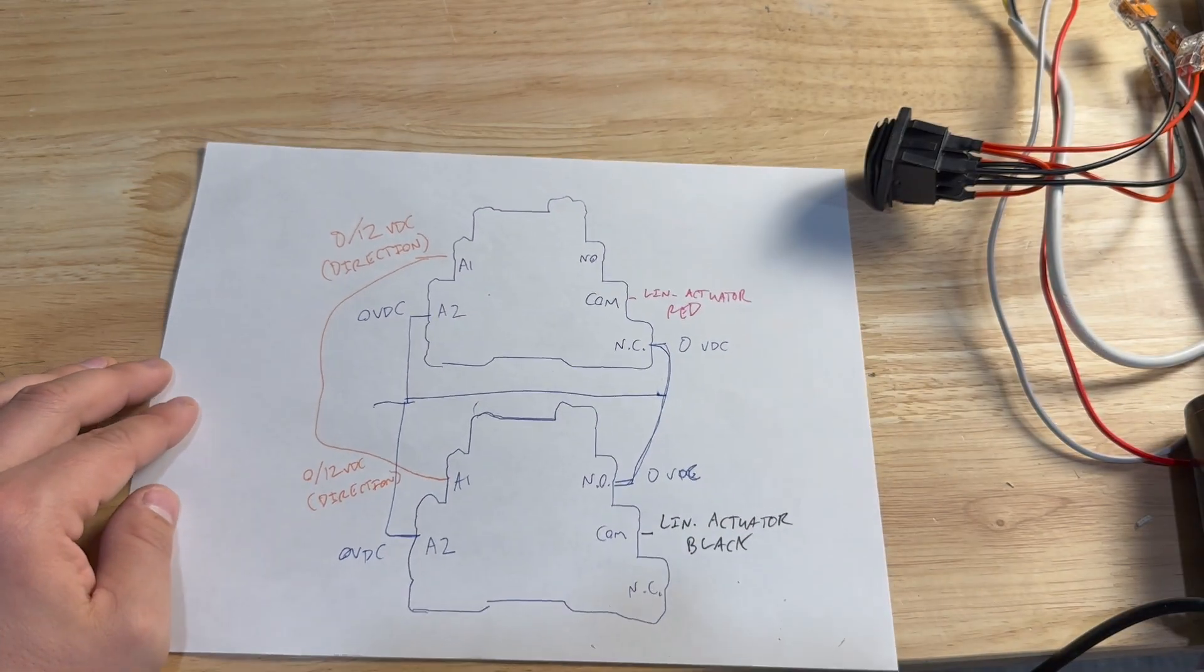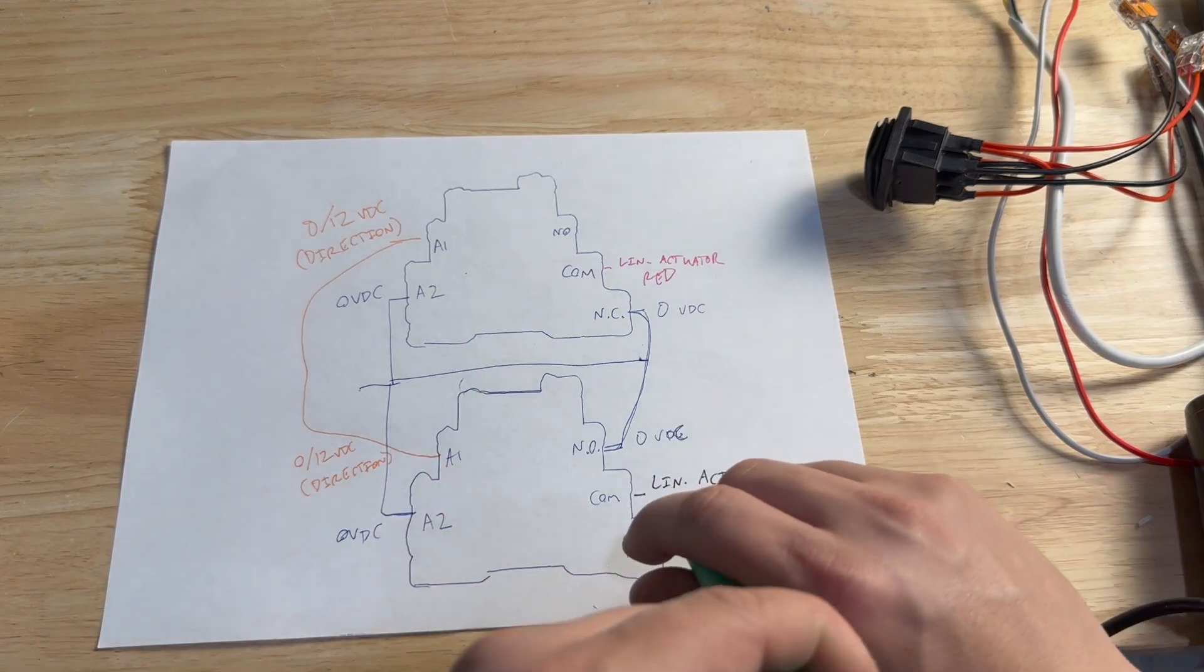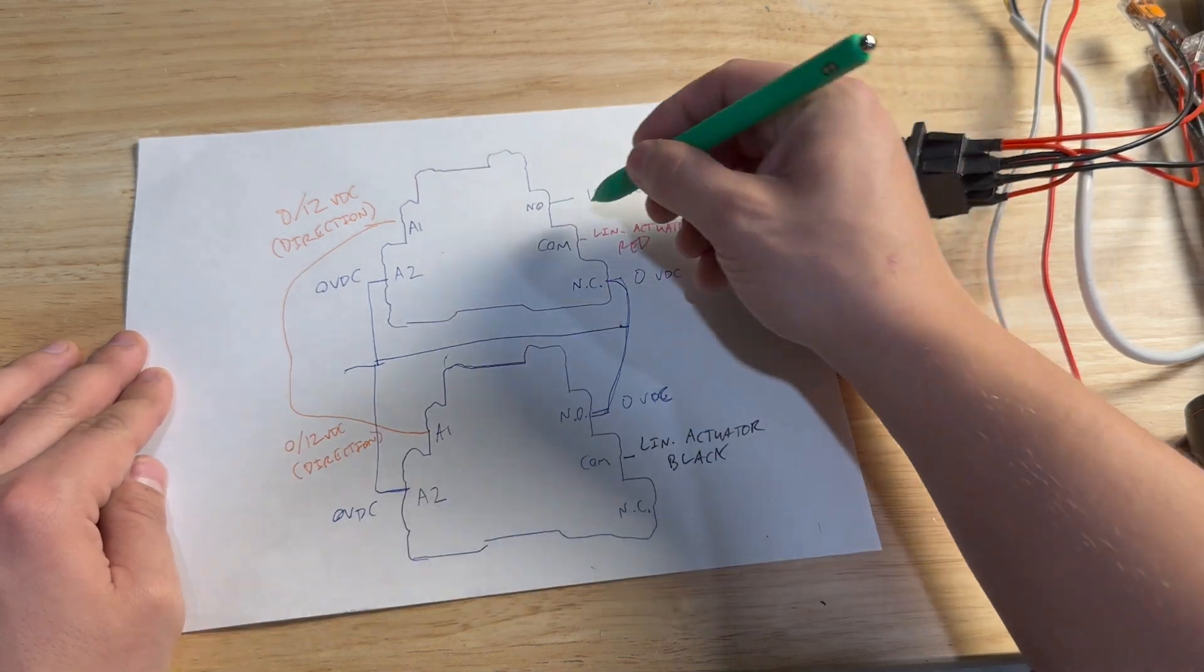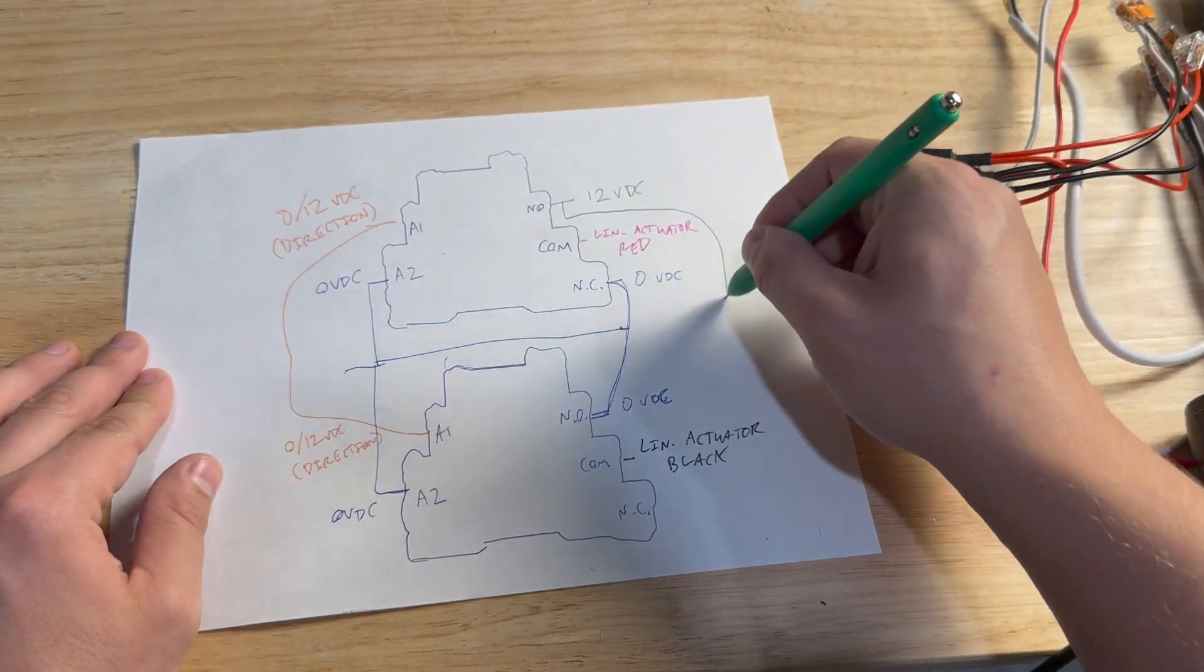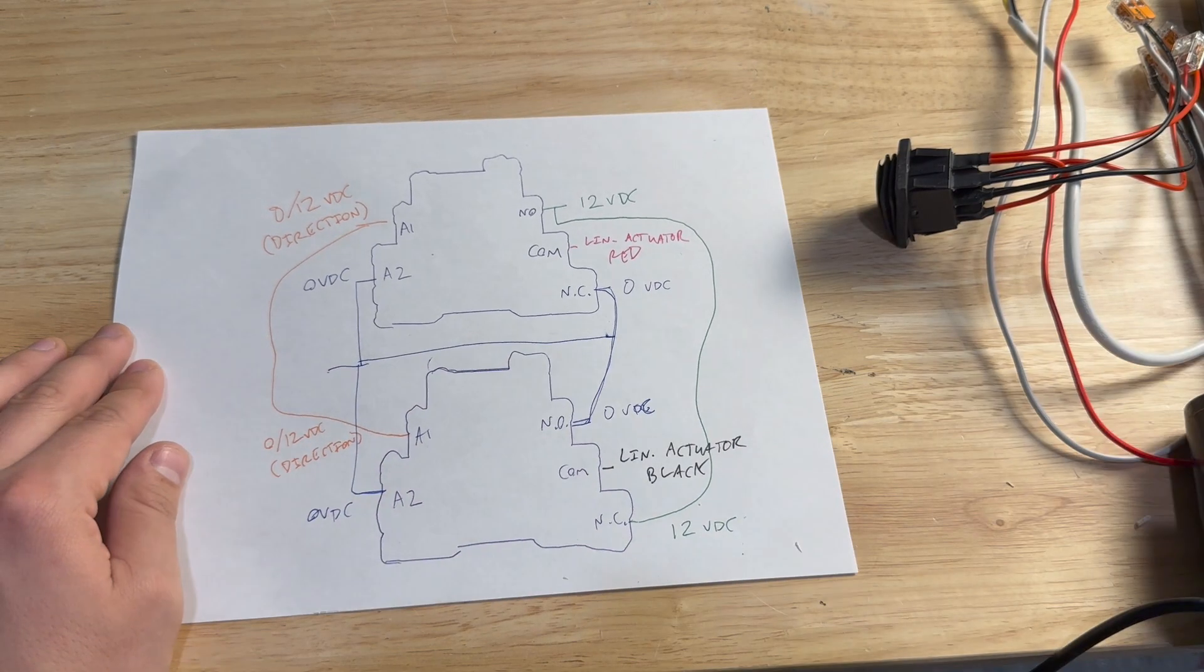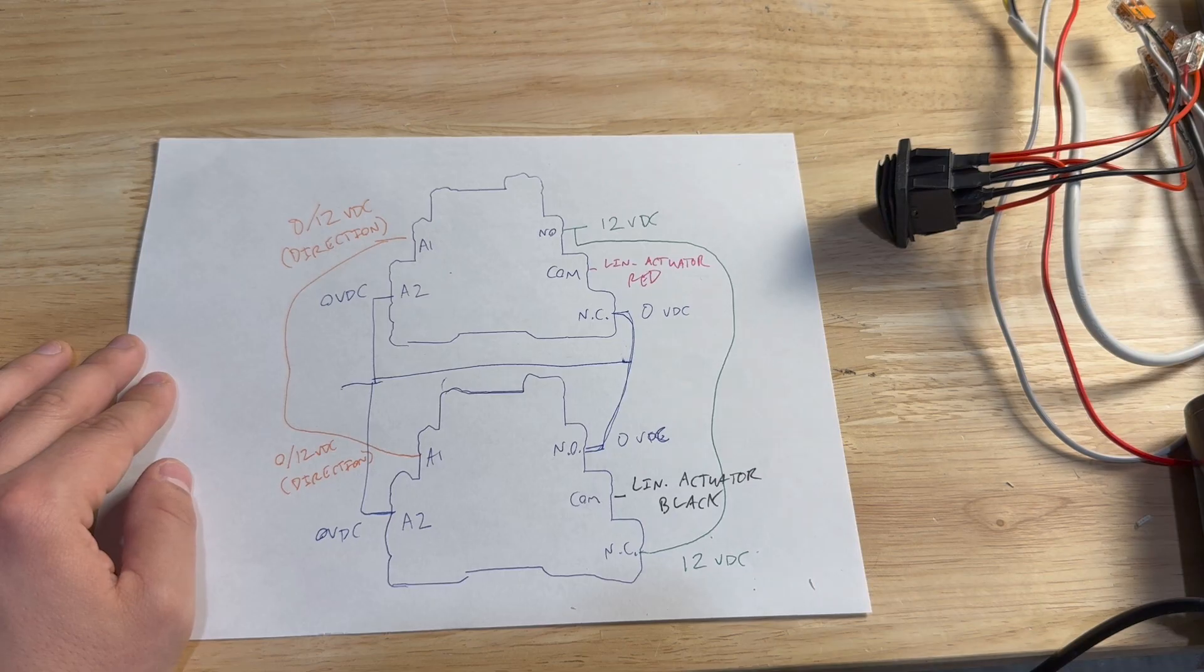But since I need to achieve directional switching, I need positive power on normally closed for one relay, and I'll jumper that to normally open on the other relay. Then I land 0 volts DC on the other normally open or normally closed terminal and jumper those together too. So now as long as I energize these relays at the same time, the actuator will switch directions with the state of the relay. This means I can use the signal from my PLC or microcontroller of either a one or a zero, to mean forwards or reverse, and jumper it to both relays so that it switches at the same time.